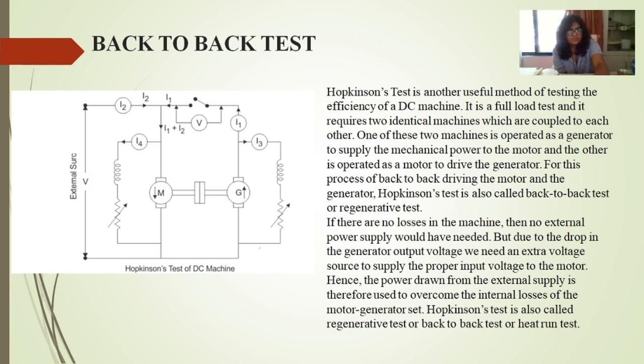Hopkinson test is a useful method of testing the efficiency of the DC machine. It is a full load test and it requires two identical machines which are coupled to each other. As you can observe in the figure, two machines are coupled to each other. One of these is operated as a generator, in the figure it's labeled G, to supply the mechanical power to the motor, and the other is operated as a motor, as you can observe, M, it's noted M in the figure. For this process of back-to-back driving the motor and the generator, Hopkinson test is also called back-to-back test or regenerative test.